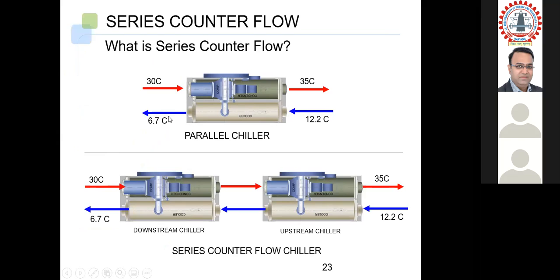And then it cools down that water to 6.7 degrees centigrade. Then this water is supplied to the air handling units or fan coil units, which goes to the air handling unit coil, cools down the space and brings it back at 12.2 degrees centigrade. So this is the indoor part of the cycle. Second, 30 degrees centigrade and 35 degrees centigrade is the outdoor part of the chiller. This water goes to the cooling tower, cools down, and re-enters the chiller at 30 degrees centigrade. So this is the typical cycle that operates with a chiller.